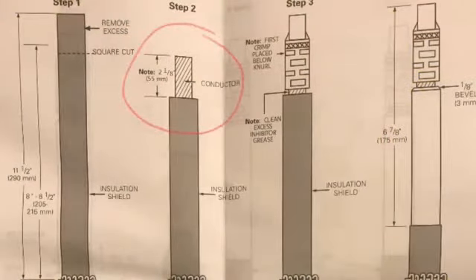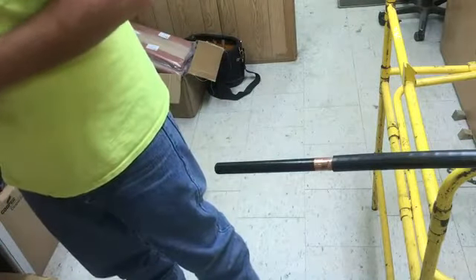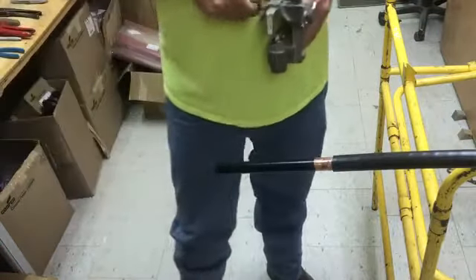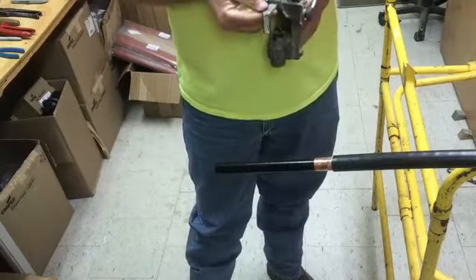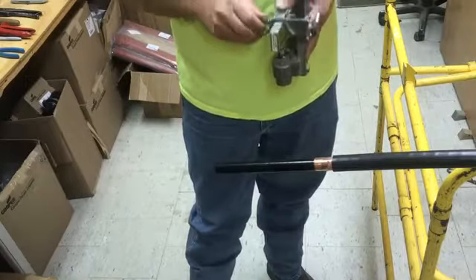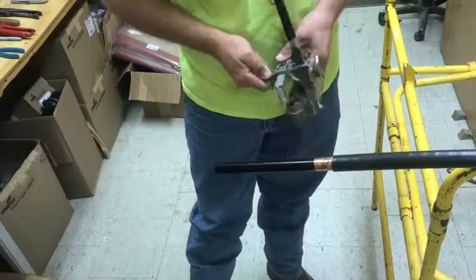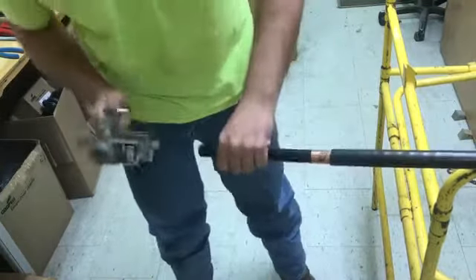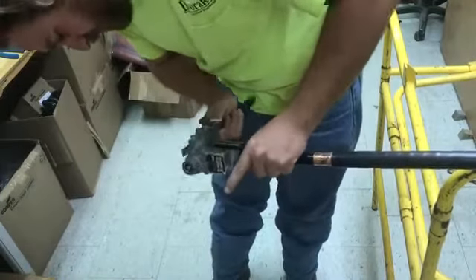I'll now perform the insulation cutback. According to the instructions, the cutback length is 2 1/8 inches. I'll take my insulation stripping tool, set the blade depth as well as the cutback length to 2 1/8 inches, and perform a practice cut backwards as to not cut into the cable to verify that the blade depth will not penetrate through the insulation into the copper.